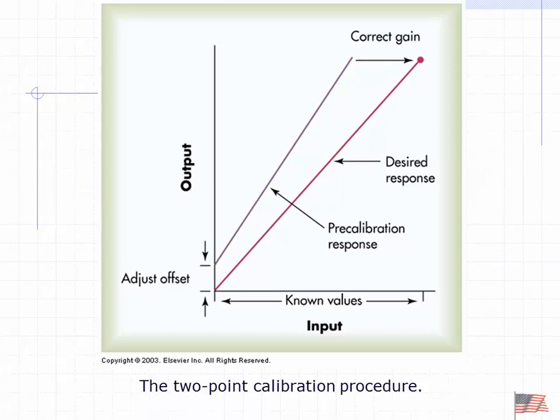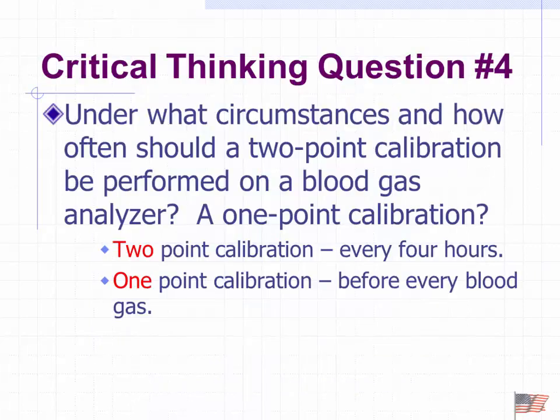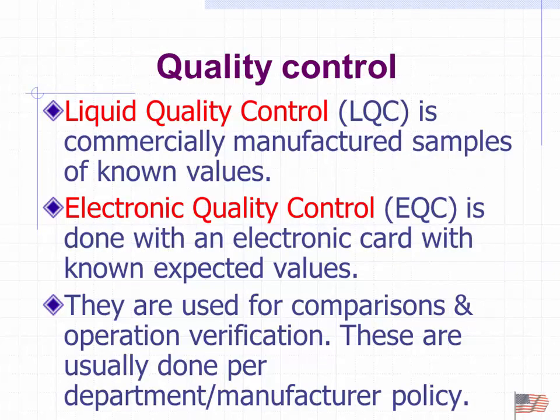So what does it do? It internally goes ahead and tweaks it a little bit until it gets to that point. Okay? That's a 2-point calibration, a high point and a low point. And we typically do a 2-point calibration every 4 hours, and a 1-point is done prior to every blood gas. So that's calibration.